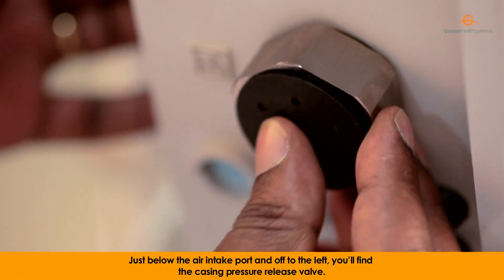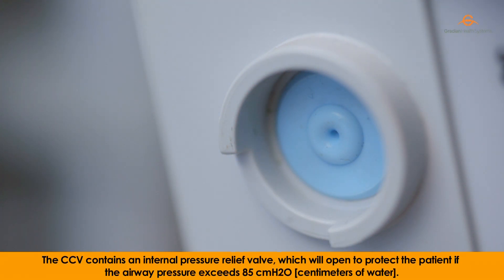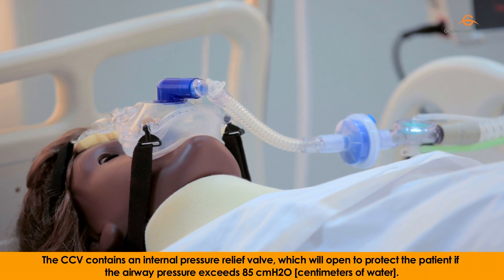Just below the air intake port and off to the left, you will find the casing pressure release valve. The CCV contains an internal pressure relief valve which will open to protect the patient if the airway pressure exceeds 85 cm of water.